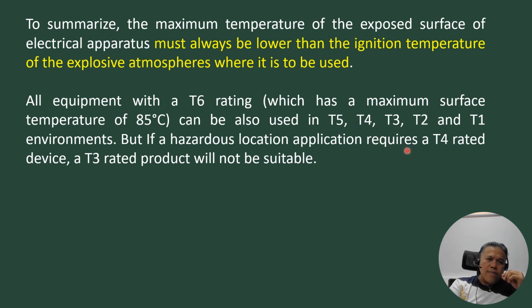So for a hazardous location application, you're buying equipment with temperature class T4 rated device, and then a T3 rated product will not be suitable. So you cannot use T3, 2, 1. Okay.